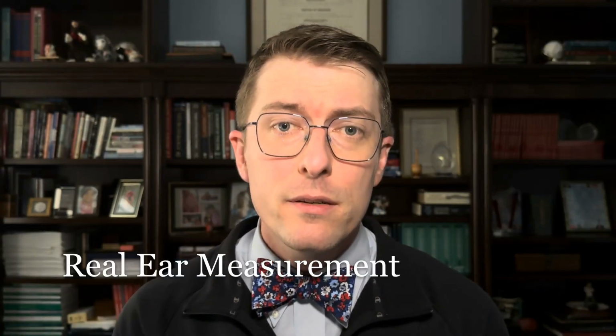The purpose of real ear measurement is to verify or check that the hearing aids are amplifying appropriately for your hearing loss. It's a much more precise way of doing it than just asking, how does it sound? To complete real ear measurements, the audiologist will place a small microphone into the ear canal past the hearing aid. This will likely feel a little awkward. It might tickle or even make you cough. And then you'll hear some speech samples played through a speaker in front of you. This will be played likely a few times at different volumes. And although this part may get a little repetitive, this part is crucial because it allows the audiologist to confirm and verify that the hearing aids are doing what they need to be doing.